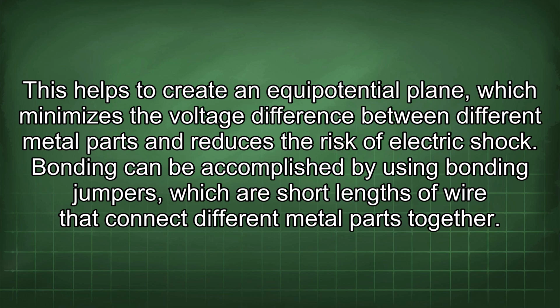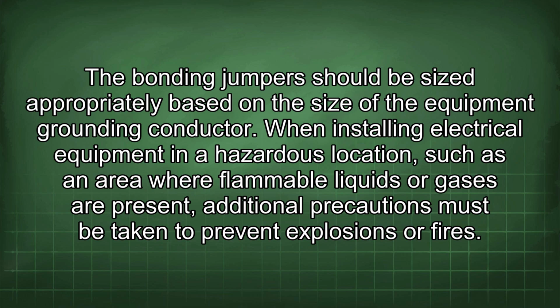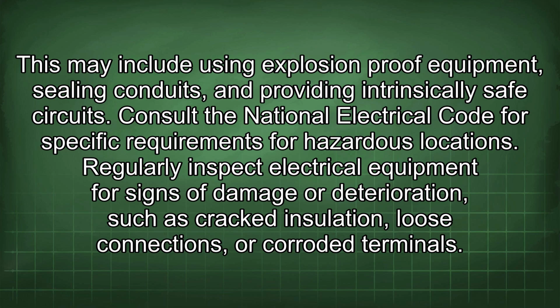Bonding can be accomplished by using bonding jumpers, which are short lengths of wire that connect different metal parts together. The bonding jumpers should be sized appropriately based on the size of the equipment grounding conductor. When installing electrical equipment in a hazardous location, such as an area where flammable liquids or gases are present, additional precautions must be taken to prevent explosions or fires. This may include using explosion-proof equipment, sealing conduits, and providing intrinsically safe circuits. Consult the National Electrical Code for specific requirements for hazardous locations.